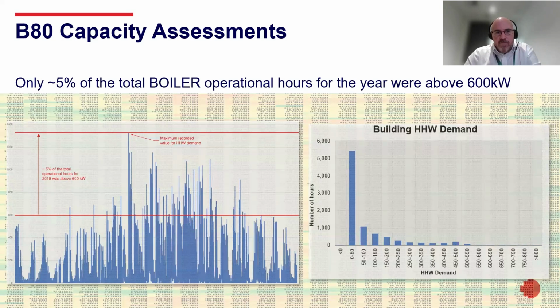Looking at the capacity, only 5% of the boiler operational hours were above 600 kilowatts. So that's another important one in terms of understanding the staging and the sizing. So you can see on the graph there with the red lines, we went with two 600 kilowatts in the end, which basically provided full redundancy for the 95% of the year and the ability to service the peak for the entire year, with the exception of design days as an example, where the outdoor temperature is quite low, but also there's some defrost and some other things that are limiting the capacity of the heat pumps. So under those instances, we've elected in this case to maintain the boiler in situ, just in case. But the intent is that it will not be required in day-to-day use once we've been through a controls rationalization.